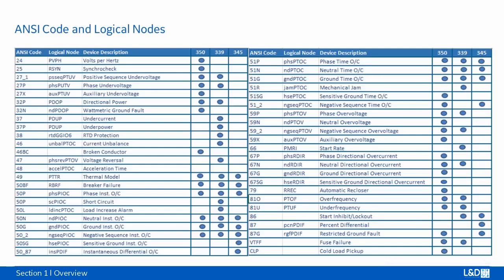From this table we can see, for each type of relay, what functions are available, and the IEC 61850 logical node is also provided. For example, we can see that the current elements 50P, 50 breaker failure (BF), neutral and ground, and negative sequence are common for all three relays. Same for the time overcurrent, phase and neutral and ground. And some protection elements are unique to certain relays.